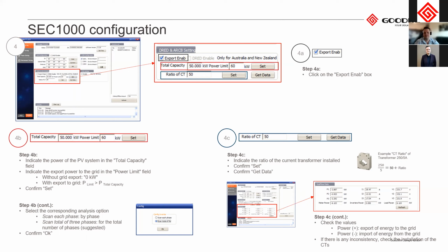So these two options, what scan each phase means, scan each phase is lowest phase limiting. So it means it will limit the plant by the lowest usage. So that means total 0 export. We will not export any power to the grid. We'll only produce as much power as the lowest phase is using. And then scan total of the phases, that is our average phase limiting. So it will take an average of the 3 phases usage and produce to that average.